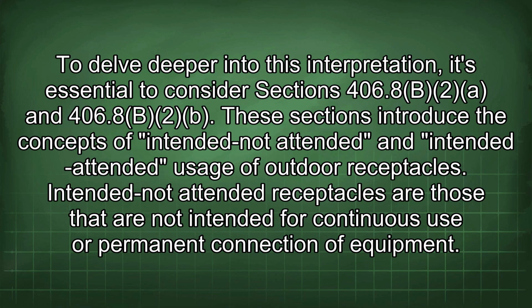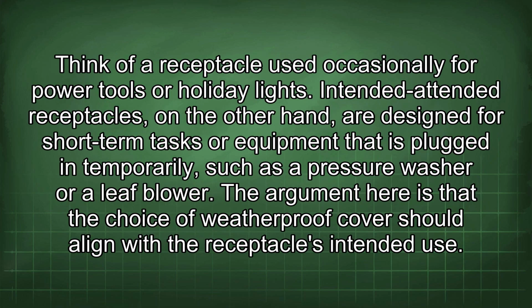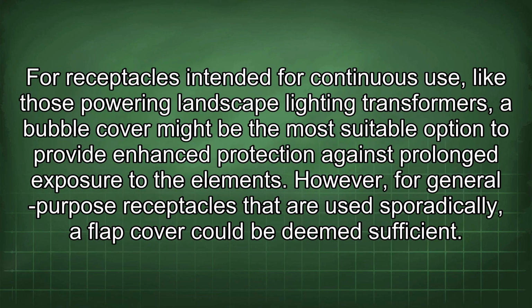Intended not attended receptacles are those that are not intended for continuous use or permanent connection of equipment. Think of a receptacle used occasionally for power tools or holiday lights. Intended attended receptacles, on the other hand, are designed for short-term tasks or equipment that is plugged in temporarily, such as a pressure washer or a leaf blower. The argument here is that the choice of weatherproof cover should align with the receptacle's intended use. For receptacles intended for continuous use, like those powering landscape lighting transformers, a bubble cover might be the most suitable option to provide enhanced protection against prolonged exposure to the elements. However, for general-purpose receptacles that are used sporadically, a flap cover could be deemed sufficient.